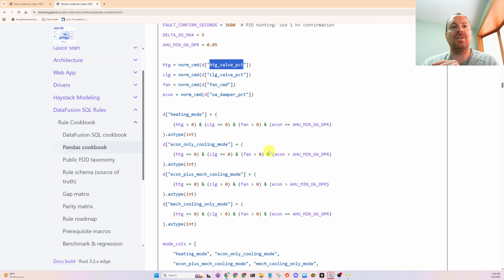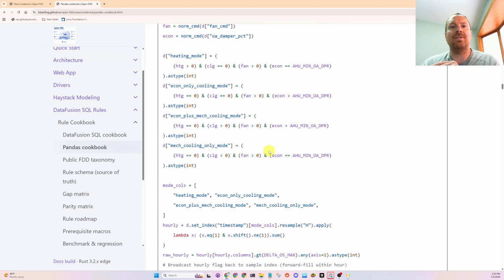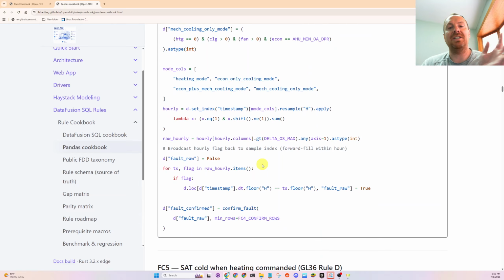ASHRAE Guideline 36 defines how many state changes the air handling unit should be going through between heating mode, cooling mode, economizing, and so on—state changes allowed per hour, which I think is 5. So if the air handling unit is oscillating between these different modes by valve and damper positions in the data, it's going to flag it.